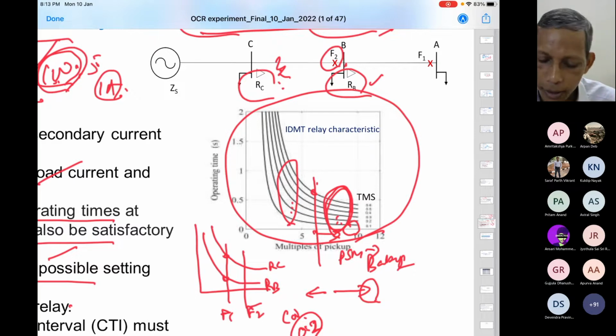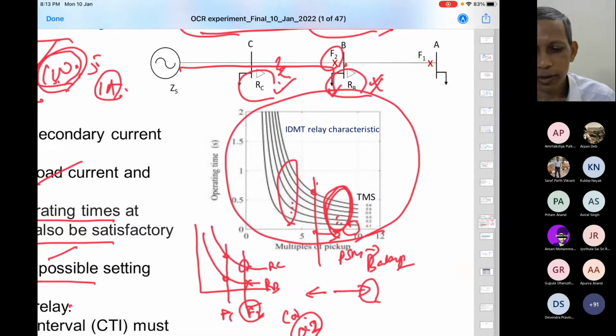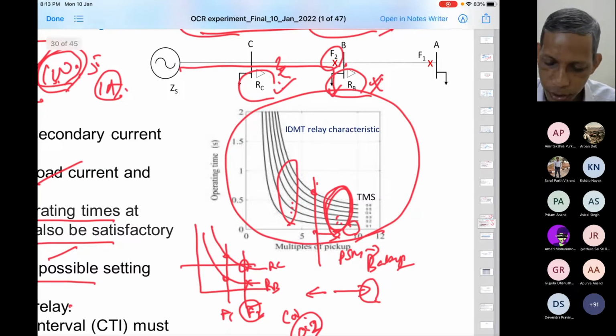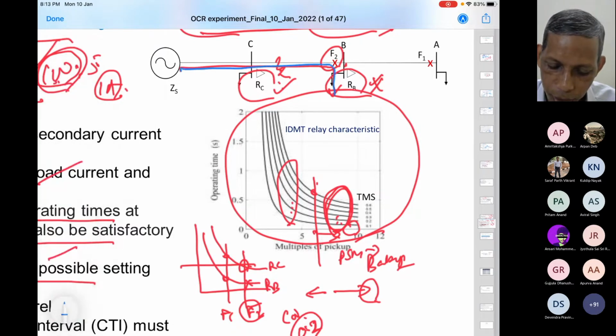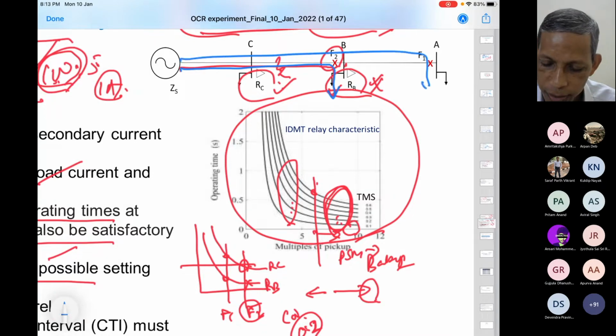Agree? For F2, who will see the fault current? RC will see, not RB. RB will not see. Only RC will see. The fault current will be this. Agree? So this F2 fault, IF2, and this is the corresponding trip time. Is it clear? Could you respond? Is it clear or not? For F2, this is the path, and for F1, this is the path. For F2, only RC will see. For F1, yes sir.